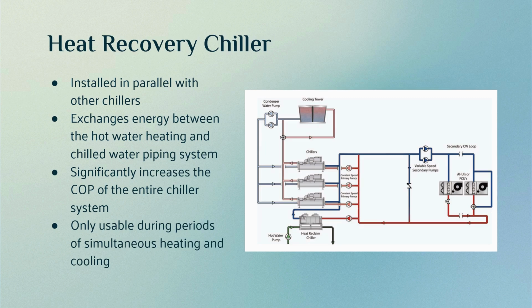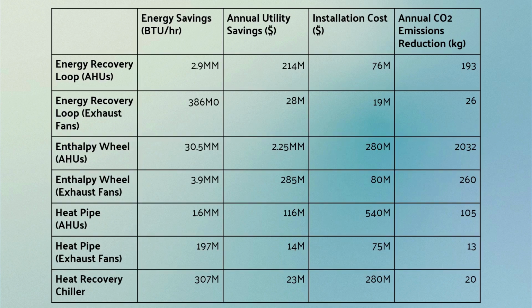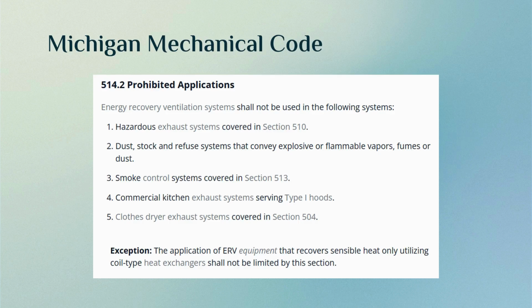However, this heat recovery chiller would only be usable during periods of simultaneous heating and cooling for the building, which would be the shoulder weather months in Houghton, so only about 4 months out of the year would this heat recovery chiller be able to be effective. So looking at our potential energy savings, our enthalpy wheel installed into the air handler units does have the highest potential savings, since that is with our highest airflow and highest heat transfer effectiveness due to that sensible and latent heat transfer.